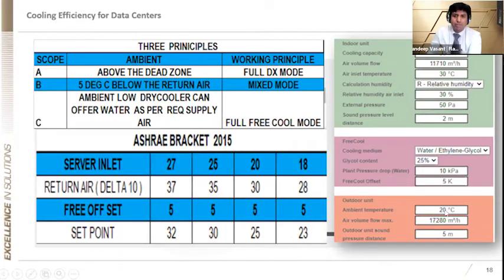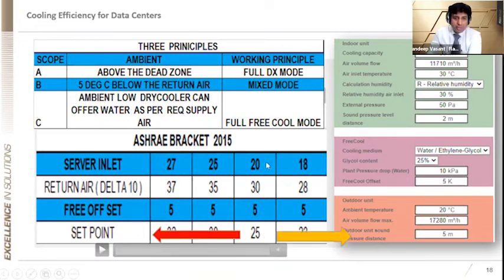Ambient is low, I've taken it at 20 just for our discussion purposes. So if you see the supply air temperature at 20, return air delta T of 10, minus 5 offset temperature, gets you 25. So let's say if we operate at this gradient, we can go up to this gradient, as I said, just for our understanding of this indirect free cooling. Anything above this set point would go into direct expansion. Anything below would be the mixed mode. Anything very low, where the unit can cater to the cooling, would go into the free cooling circuit.